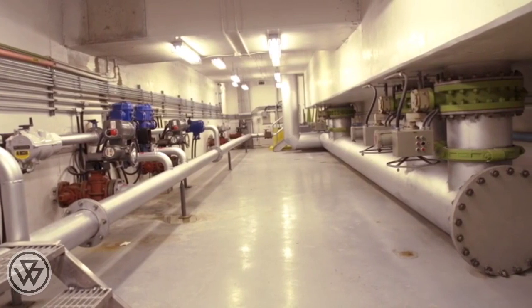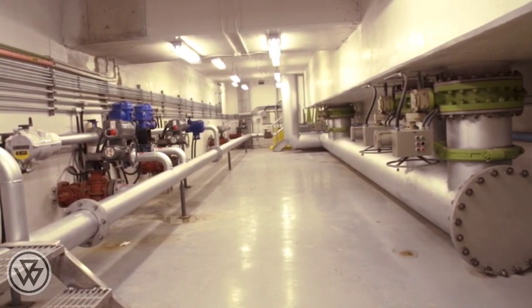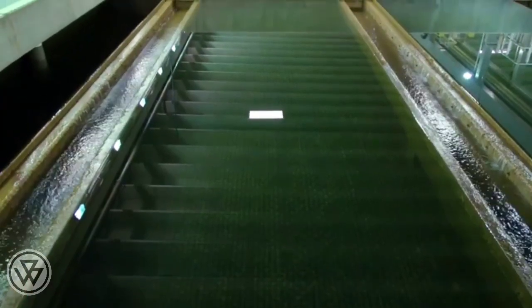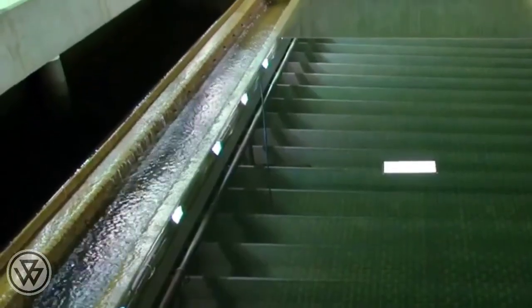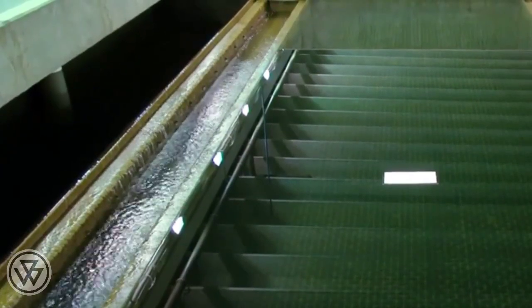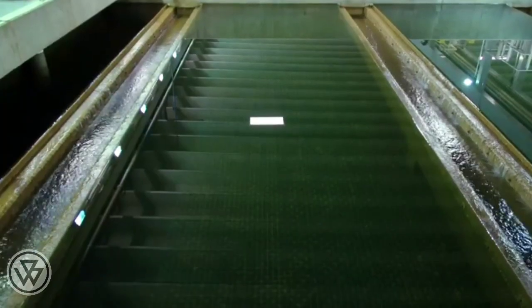The solids flow into a collection tank and are then pumped to the wastewater treatment plant for further solids thickening. Tube settlers installed in the sedimentation tanks help prevent dirt particles from being lifted up and over the collection weirs. After the sedimentation process, the water on the surface is collected on top of surface weirs. The water then flows by gravity to filters for further treatment.